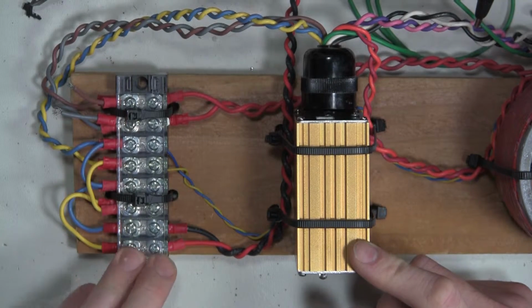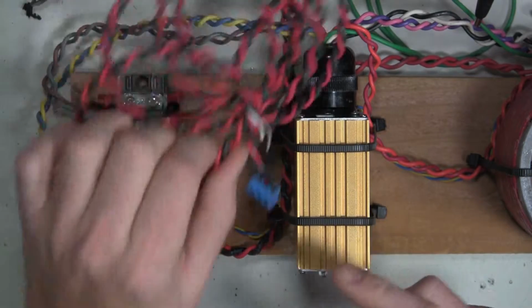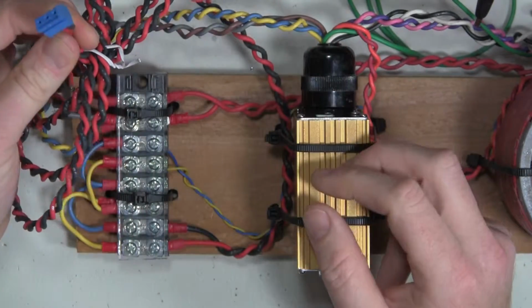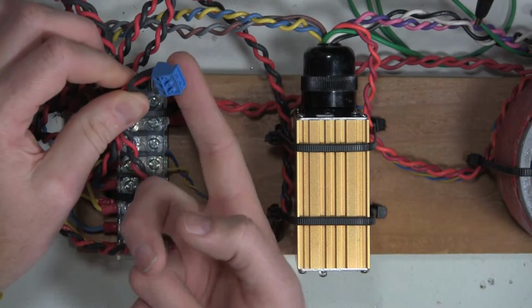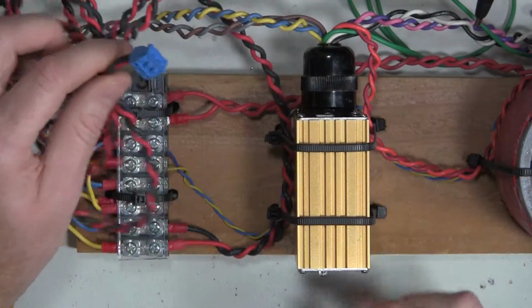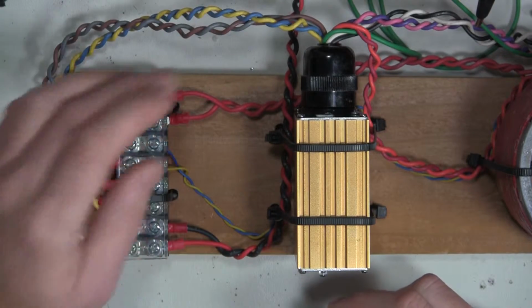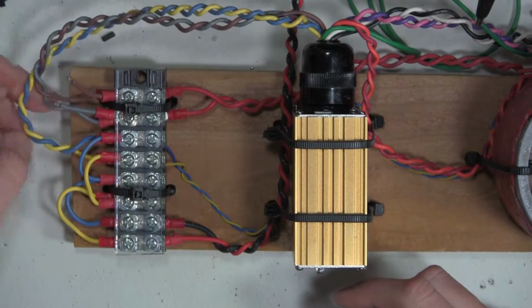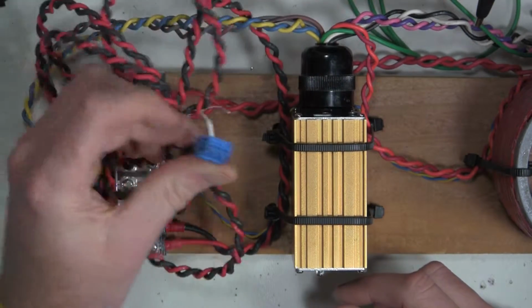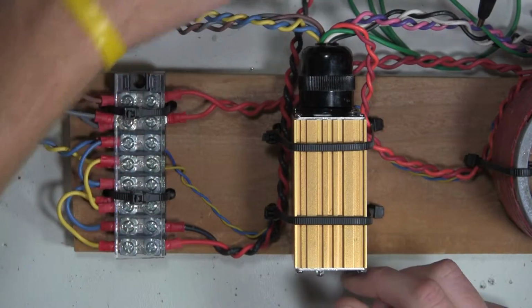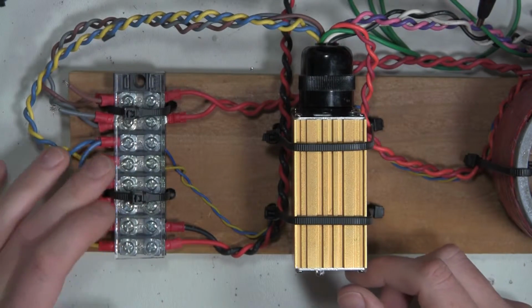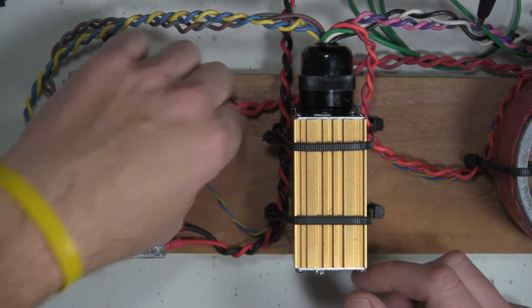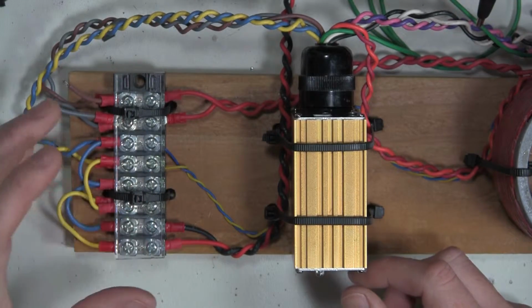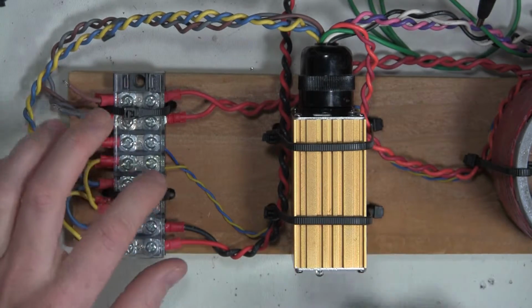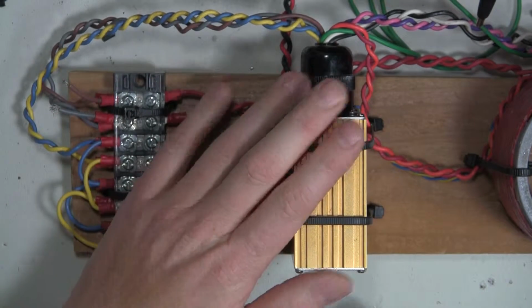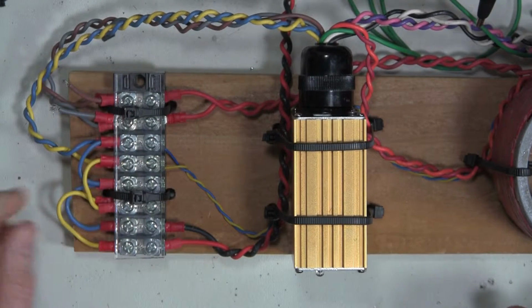And what I mean by having an input to an output is, for instance, I can take this connection right here, plug this into a call box or to a B panel, an access panel, and actually be electrically the same as the relay that's actually coming out of here. So as opposed to using this relay to close the circuit, I can use a relay from another device to close the circuit. And that's why I put so many of these jumpers. But at the same time, because they're all electrically the same, it triggers whatever device I have hooked up to it. If I want to have a call box trigger the sampler, and I want the sampler to be triggered from the loop detector, I can do that just by hooking up to one of these blue and yellows.